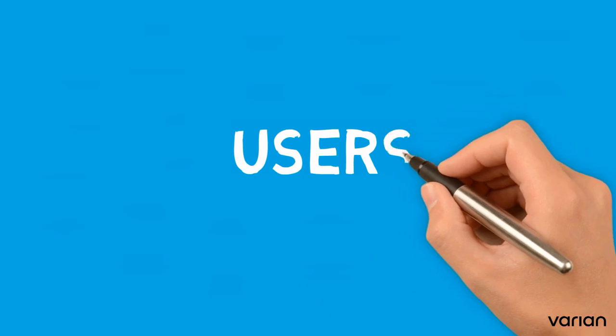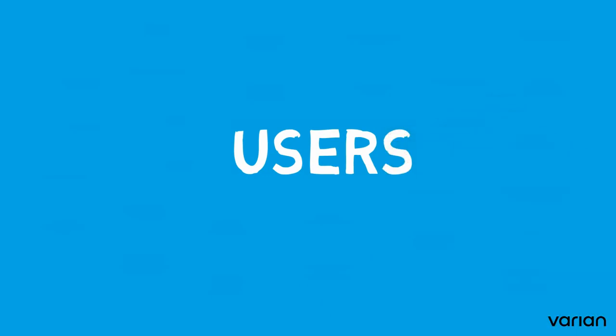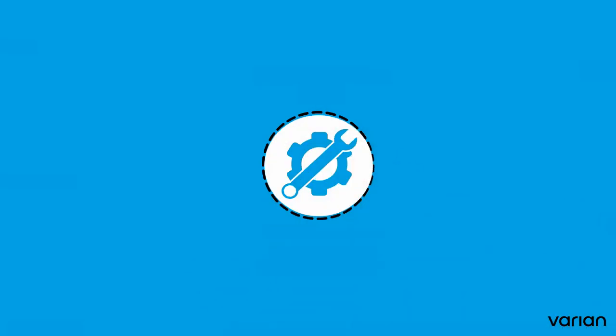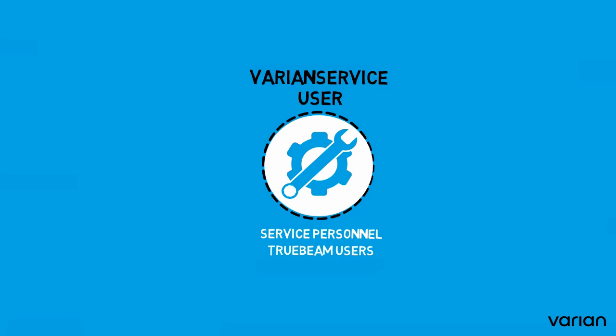We shall now look at the Varian users. The Varian service user will be required. Service personnel will have access to this user to administer and work on the system after installation is complete. This user is for the TrueBeam users to do service and maintenance on the TrueBeam. Your local service reps will also have this account to help troubleshoot Varian repair issues with the system.